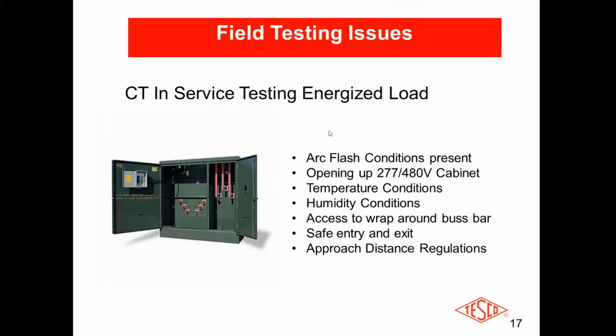I'd say in the majority of cases, this isn't a test you do every week. It's something you might do every few years, maybe once every 5 years, or annually. You need to decide which customers are the most vulnerable or sensitive, or perhaps the ones with the highest load demand, whose load changes significantly - that's when the CTs are being stressed. So it's wise to pick those maybe once a year. It might be less than 5% of your entire customer base, but it's worth doing. You don't need to test them all, but focus on the ones that are most sensitive.